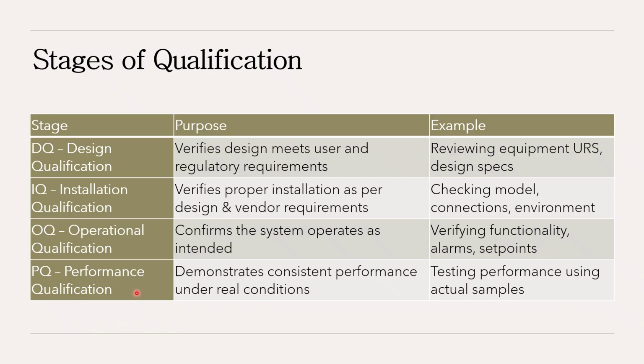Next one is the performance qualification. Performance qualification demonstrates that the equipment consistently performs as expected under actual working conditions, right? The example is using real samples or processes.